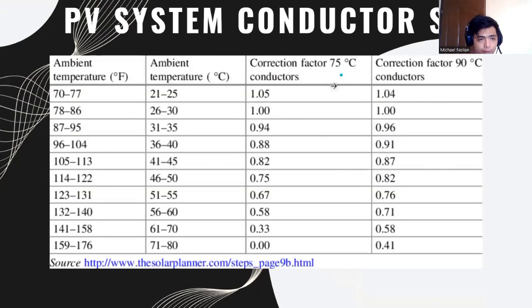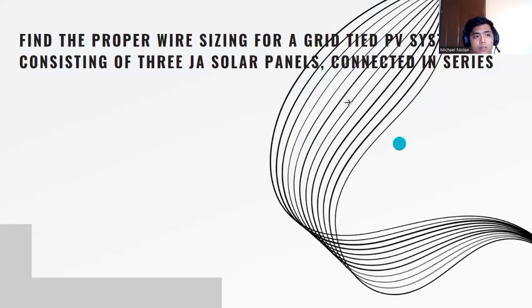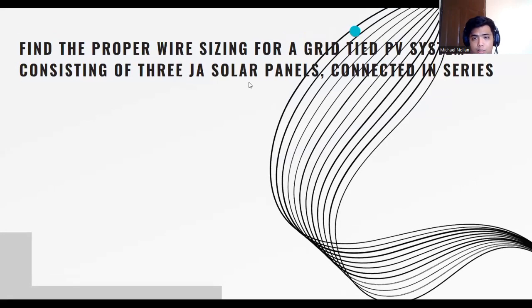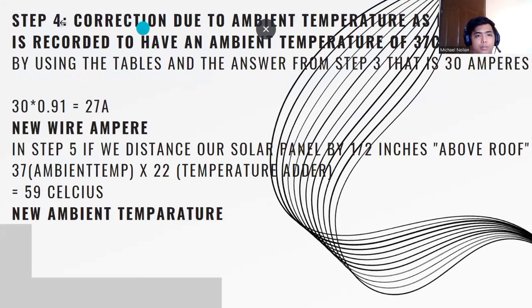Like earlier, this table gives the ambient temperature, which we will use later. Mostly we will use the 91. Okay. Find the proper wire sizing for a grid-tied PV system consisting of 3 solar panels connected in series. This is where I started after the split, and this is what was given to me. Step 4: correction due to ambient temperature, as the Philippines is recorded to have an ambient temperature of 37 degrees Celsius.